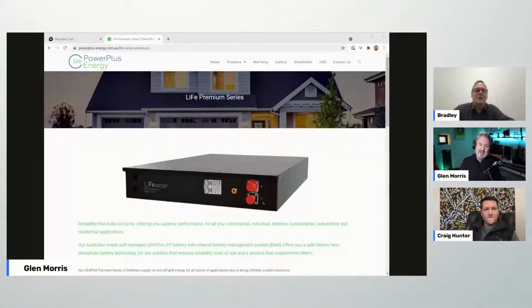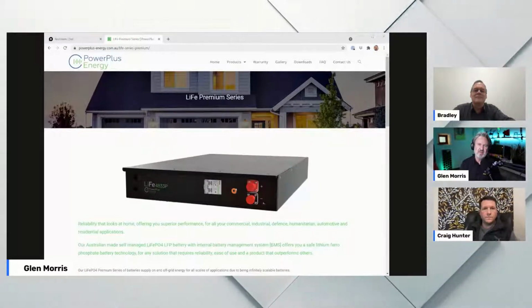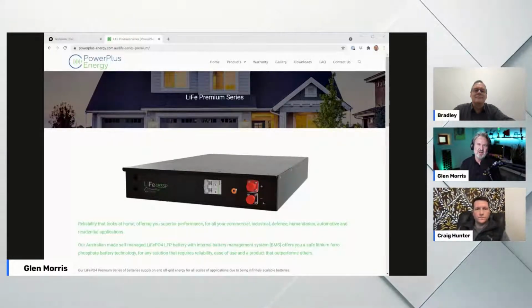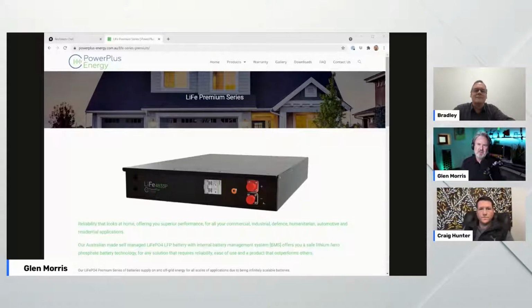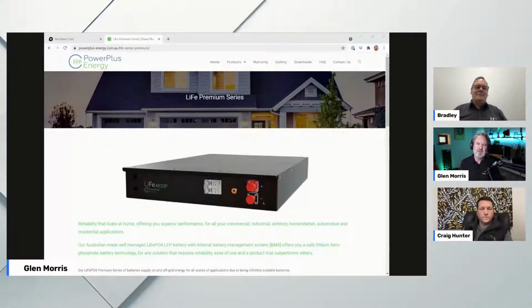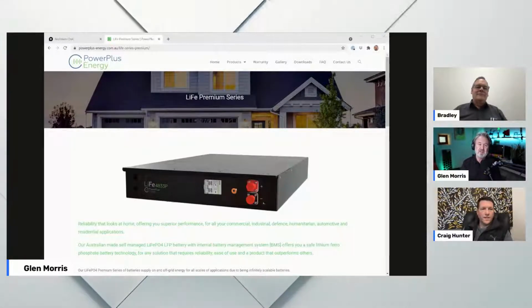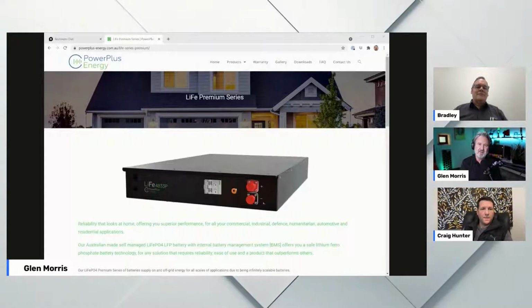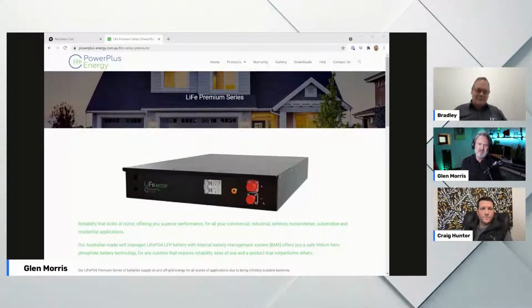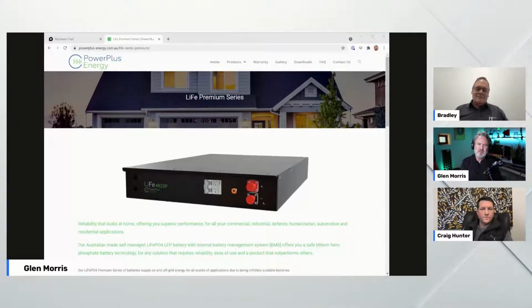Number three, you've got a Noark breaker in there, and of course that means you've got something that's compliant as a point of isolation. It can be deemed to be the battery system isolator, and it's overcurrent protection. It's lockable in the off position using a locking device because it is a circuit breaker, and it's load breaking, so it ticks all the boxes in AS NZS 5139 as the point of isolation.